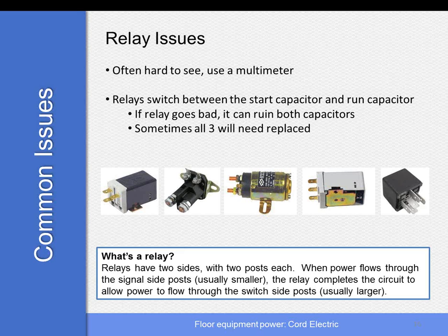Earlier I said there are some relays that are between two capacitors. The switch is between a start capacitor and a run capacitor. If that relay goes bad, it'll ruin both. And normally, especially in the case of Taski, they recommend replacing all three, both capacitors and the relay between the two, just to make it easy.